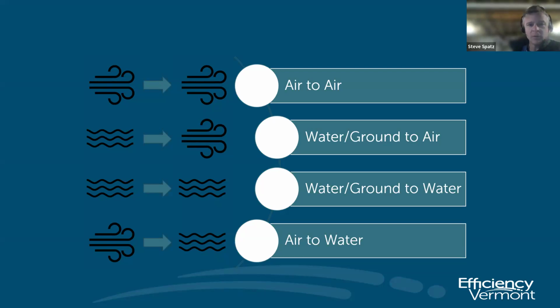So air to air, where you're essentially using the refrigerant exchange to blow air across the hot refrigerant coil, and a forced air, and that can be either a ductless wall-mounted unit and/or a forced air whole house distributed system with ductwork. Water or ground to air, same sort of thing. You're doing an exchange and using air as your distribution medium, and then air to water and ground to water. So a heat transfer occurring, heat exchange occurring, where that heat energy is then put into a hydronic distribution system. So these are all distribution option types that are allowable and efficiently achievable through using heat pumps, either air to air systems, water to air, or ground source.